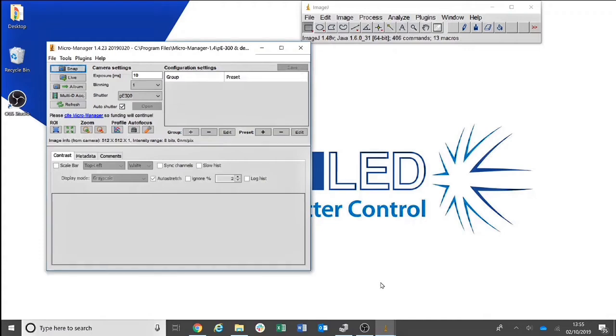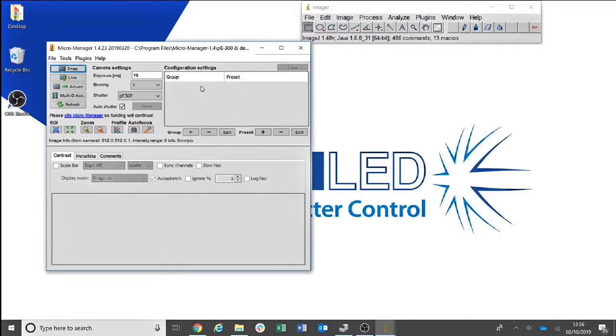Now you have the light source added to the software. You must head to Configuration Settings. Here we will set up a group that will allow you to select which channel of the light source you wish to have illuminated. We will then set up three more groups in order to control the intensity of each channel.